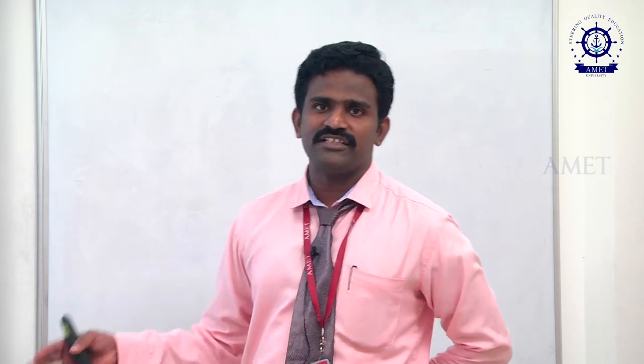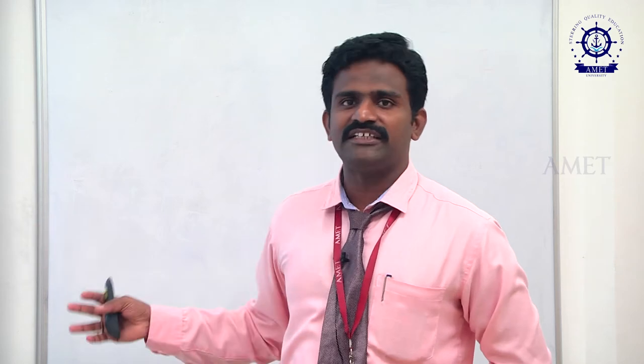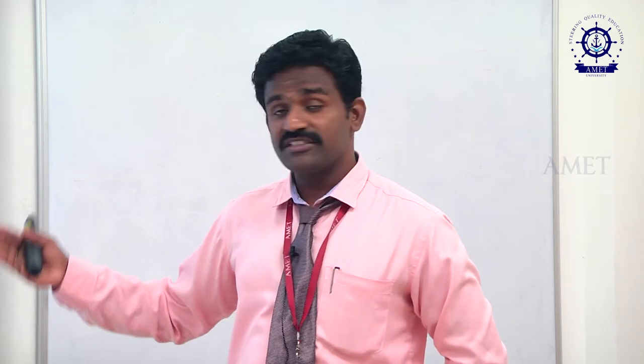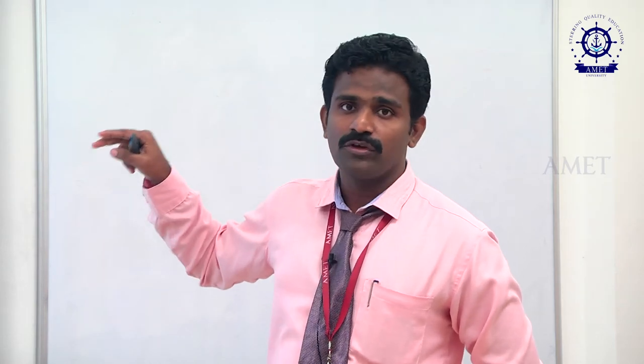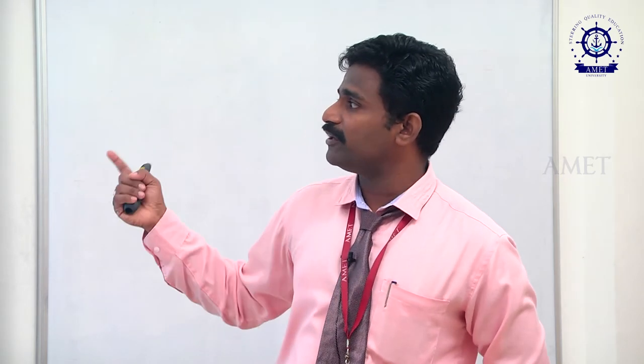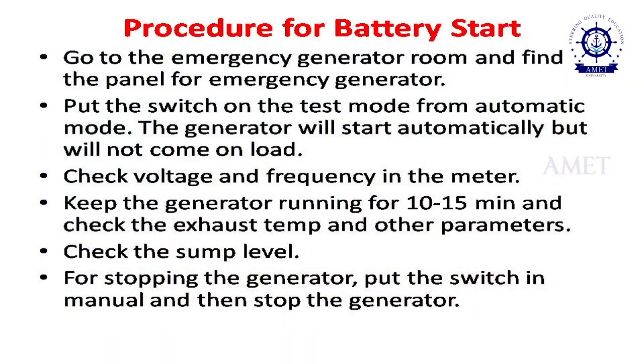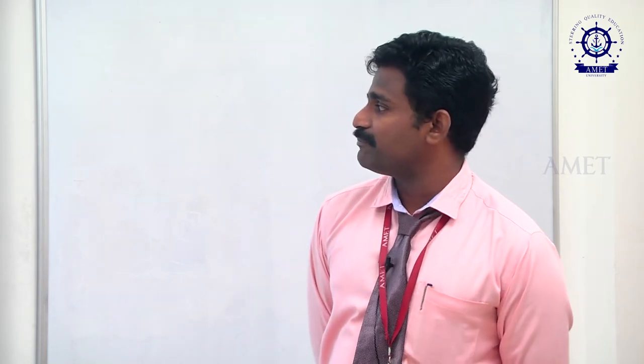When going to start for testing purposes, press test mode and turn off automatic mode. The generator will start automatically and will not come on load in test mode — no load is connected to the emergency generator during testing. Check the voltage and frequency on the meter. Keep the generator running for 10 to 15 minutes and check the exhaust temperature and other parameters — not less than 10 minutes.